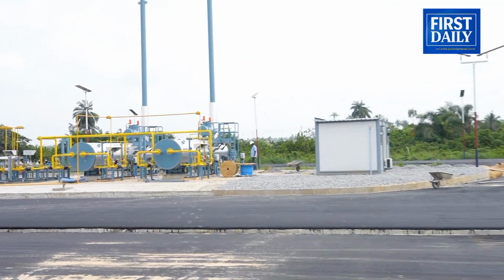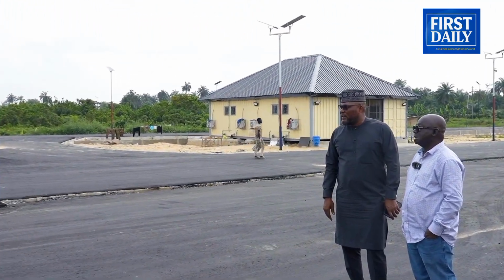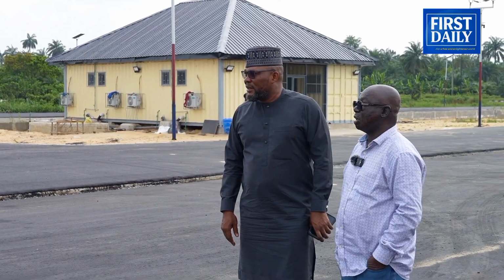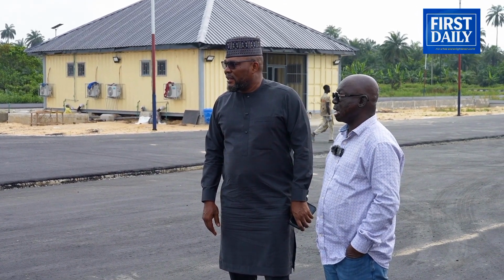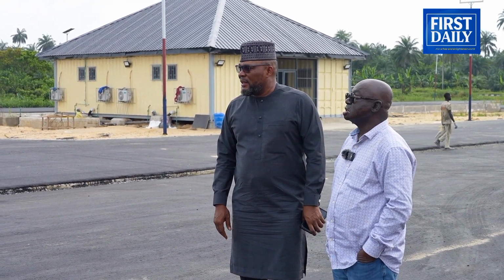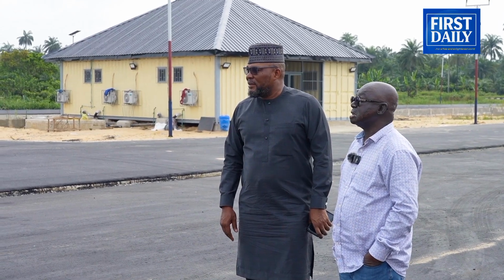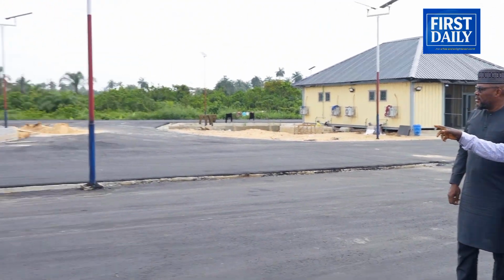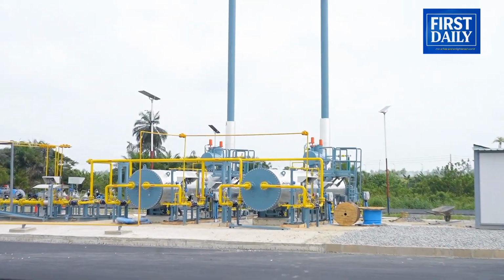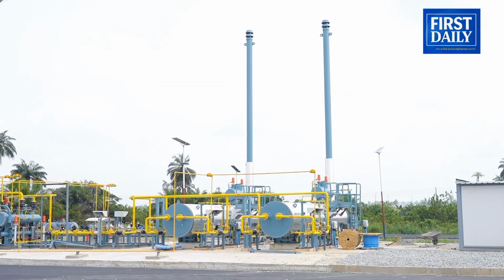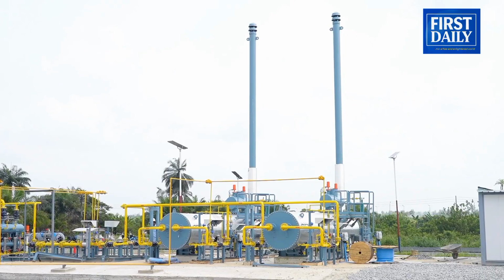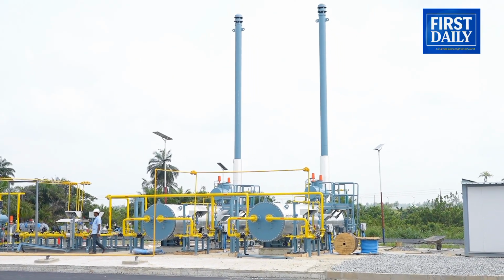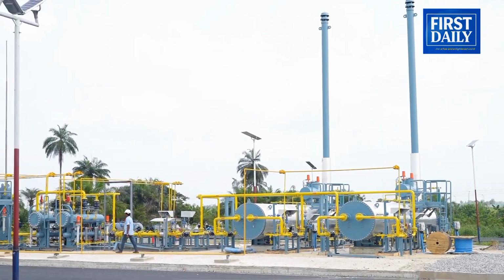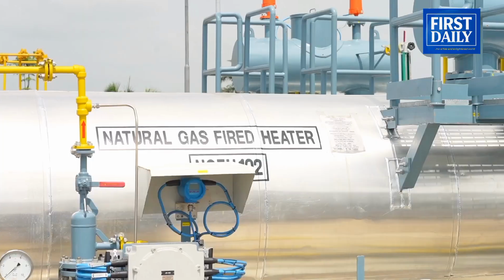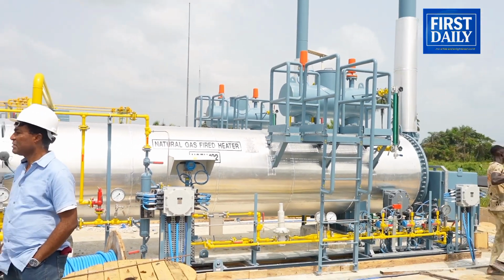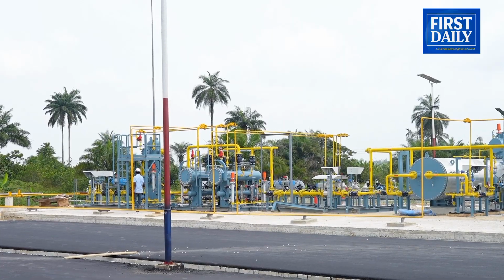Once you put the raw gas in, it knocks out all condensate — we call it a KO, the knockout drum. Then it passes through the two chambers you see there, which are heaters. It heats the gas to the required temperature for the machines before they start running. So there's reduction of pressure, removal of impurities, and heating of the gas to the required intake parameters.